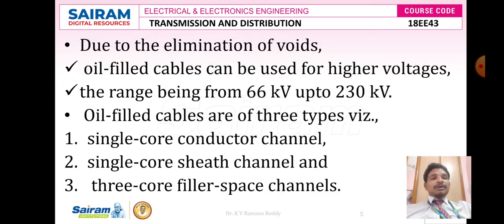Due to the elimination of voids, oil filled cables can be used for higher voltages. The range for oil filled cables is right from 66 kV to 230 kV. Oil filled cables are further classified into three types, namely: single core conductor channel, single core sheath channel, and three core filler space channels.